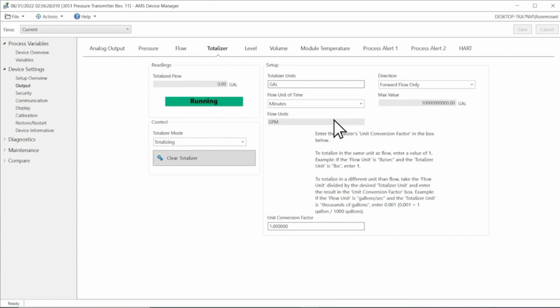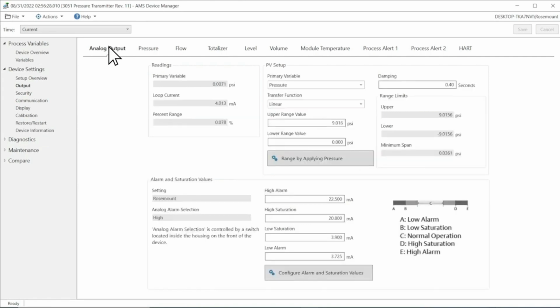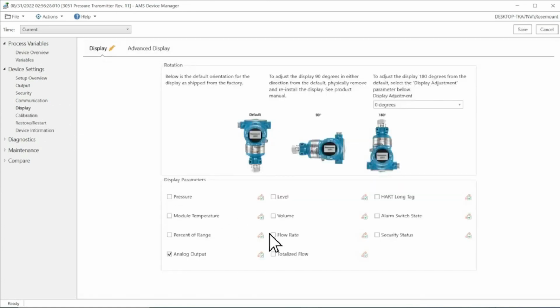To set one as the primary variable, navigate to the Analog Output menu and change the primary variable within PV Setup. Additionally, either variable can be configured to show on the display via the Display menu.